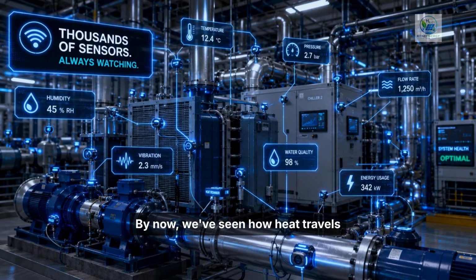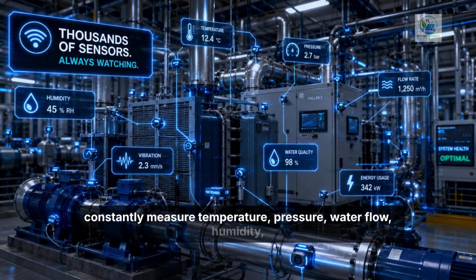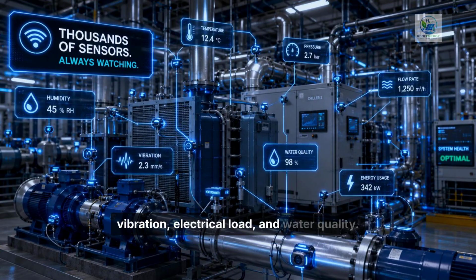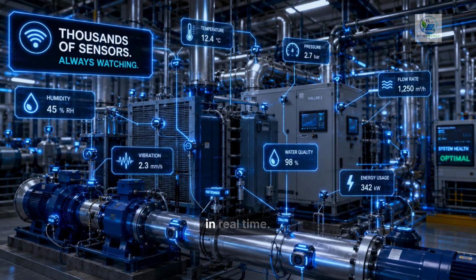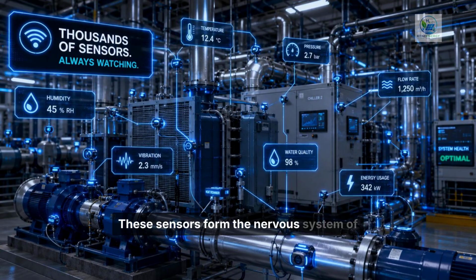By now, we've seen how heat travels from the AI processors through air, water, and the central cooling plant. But none of this infrastructure could operate safely without continuous monitoring. Throughout the data center, thousands of sensors constantly measure temperature, pressure, water flow, humidity, vibration, electrical load, and water quality. Every pump, chiller, heat exchanger, cooling tower, and server rack continuously reports its condition in real time. These sensors form the nervous system of the entire facility, providing operators with instant visibility into every part of the cooling process. If even a small change occurs anywhere in the system, it is detected almost immediately.